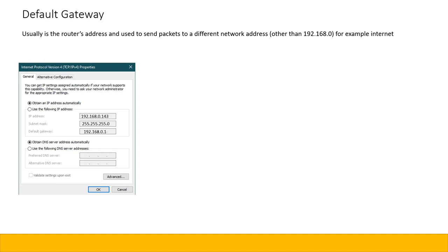If the default gateway is not mentioned, remember, when we are using PLCs or any gateway devices in our industrial networks, if various PLCs are talking to each other via a carrier, and we have a router in between, all the devices, for example, if we are using ControlWave Micro or any other device, we have to mention the default gateway address in such scenarios. Because if we don't mention the default gateway, the PLC would not have any means to know where to send its packet. So it's very important to mention the default gateway, or the router's IP address, or the gateway's IP address, inside the PLC. And usually it's given inside the PLC.